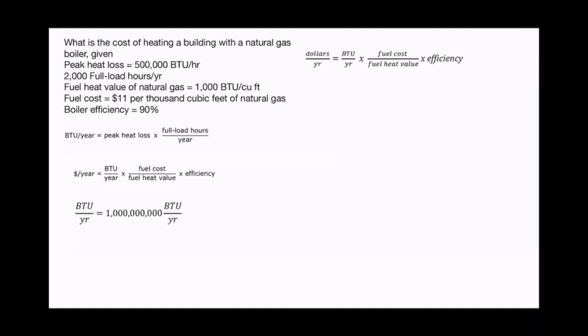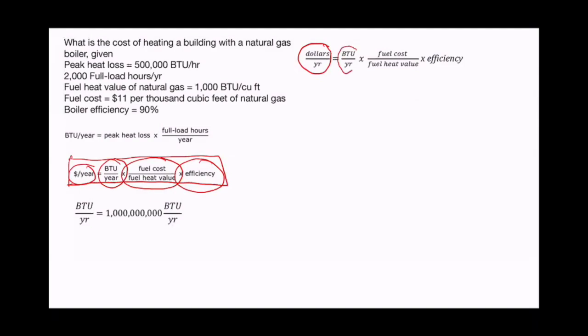Now that brings us to our second formula that we're given, which is our dollars per year is equal to our BTUs per year times our fuel cost divided by our fuel heat value times our efficiency. Now, as always, don't just look at that and say, okay, got it. Just really get it. Well, how much money do you spend per year on heating? Well, if we double our BTUs per year, if we double this to 2 billion, then you can imagine we would spend twice as much.